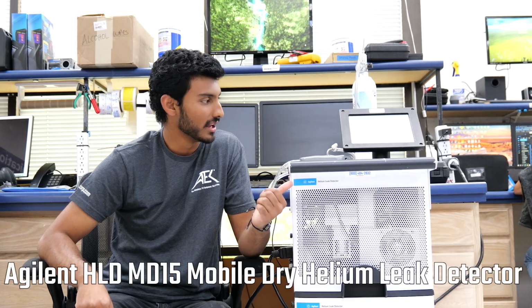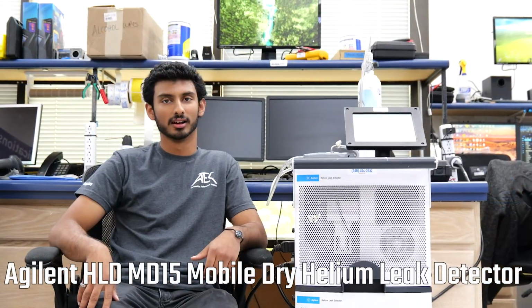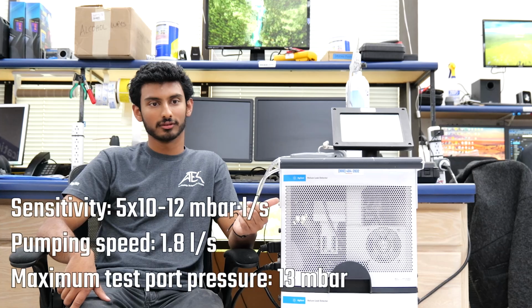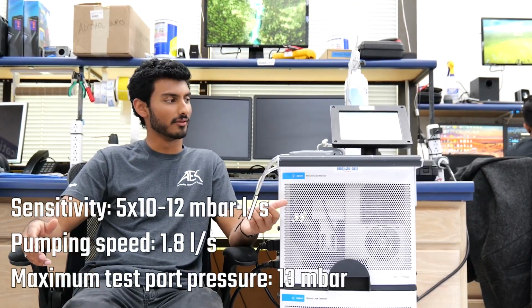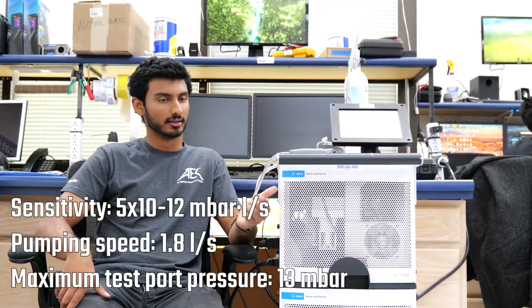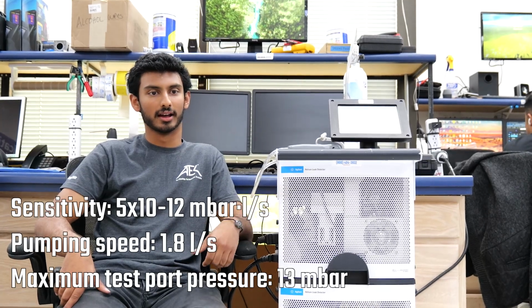My name is Vay, and today we're looking at the Agilent HLD MD15, a highly sensitive helium leak detector, which is great for industrial, R&D, and quality control environments. Whether you're looking for vacuum integrity for high vacuum rated products, this helium leak detector is great at doing accurate, fast, and reliable readings.